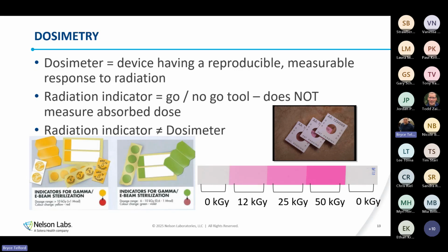So we contacted the sponsor of the study and we said, hey, it looks like you sent us sterile product for testing. We can't test sterile product. We need you to send us non-sterile product for testing. And they were very insistent that they had sent us non-sterile product for testing. And there was some back and forth. We even took photographs of the red dot indicators to show them, no, your product is showing a red dot, which is an indication that it's been exposed.